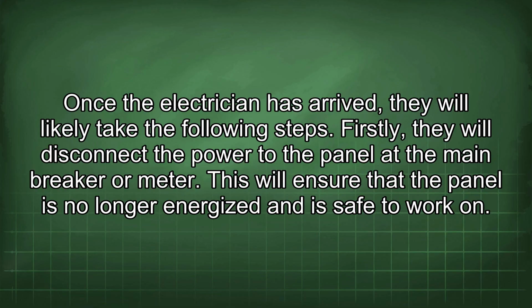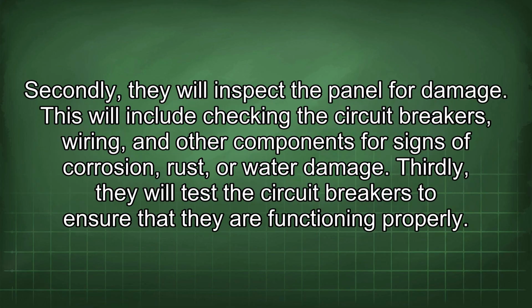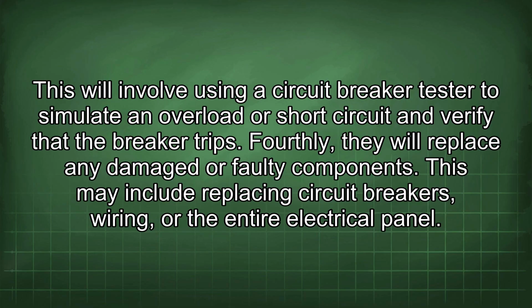Firstly, they will disconnect the power to the panel at the main breaker or meter. This will ensure that the panel is no longer energized and is safe to work on. Secondly, they will inspect the panel for damage. This will include checking the circuit breakers, wiring and other components for signs of corrosion, rust, or water damage. Thirdly, they will test the circuit breakers to ensure that they are functioning properly.